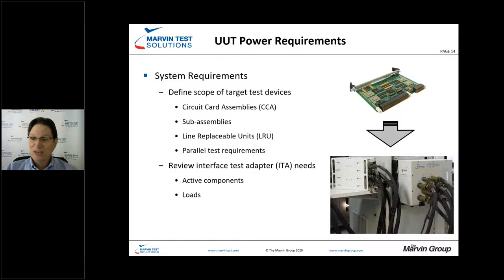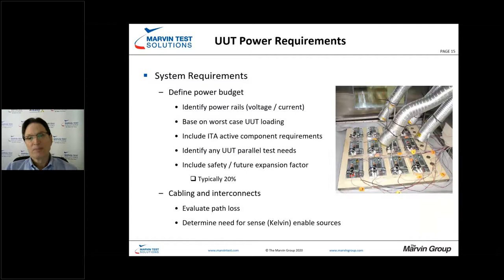ITAs often contain active circuitry. While the goal is typically to avoid active circuitry in the ITA, requirements change, and rather than modifying the entire test system, it may make sense to put active circuitry into the ITA. That all becomes part of our UUT power requirements budget. For HALT/HASS parallel testing you can see a good example on the right-hand side of the screen.